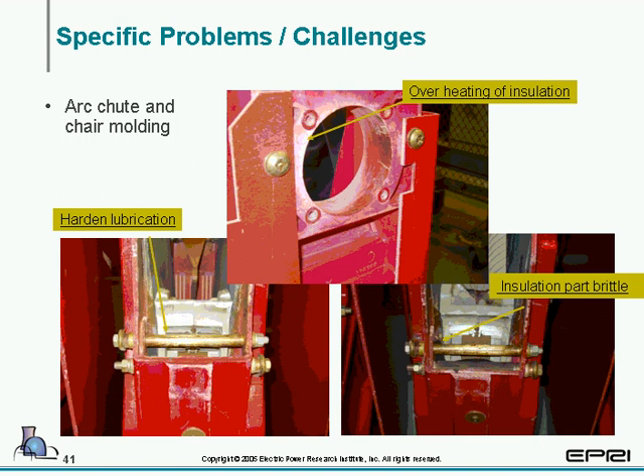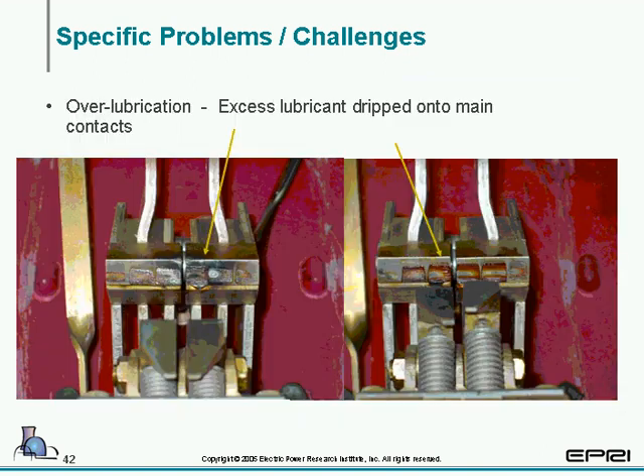As we tore the breaker apart, we could see specific problems with the insulation material. Overheating of the insulation, where the actual arc chute bolts to the upper lead, more hardened lubrication, and the back parts where the insulation material around was actually broken and brittle. And here we have a closer look at the over-lubrication, where it had dripped onto the mains.